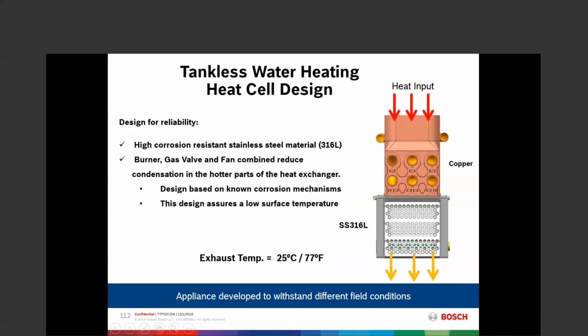So the water pushes from these 50 tubes into that bay, gets picked up by these 50 tubes where it's brought from the right-hand side back to the left-hand side, second pass through the condensing heat exchanger. And then on the left-hand side, there's another bay, and this bay covers second pass and third pass. So again, we're not taking a 180-degree turn with it through copper, through stainless steel tubing. We are just dumping into a bay, gets picked up by another 50 tubes.